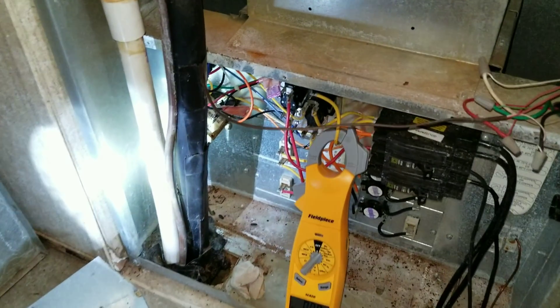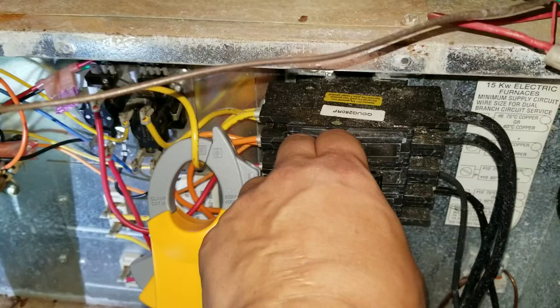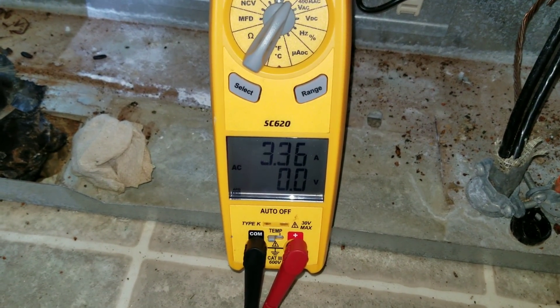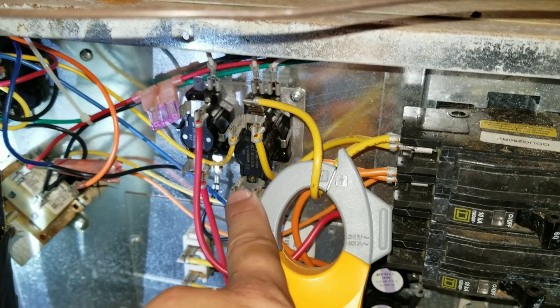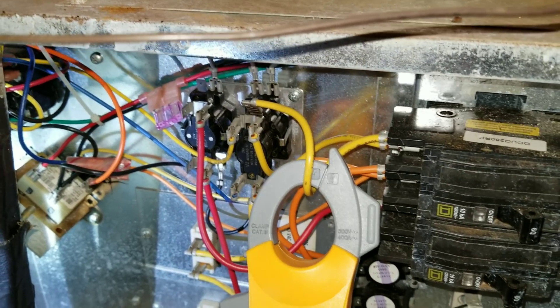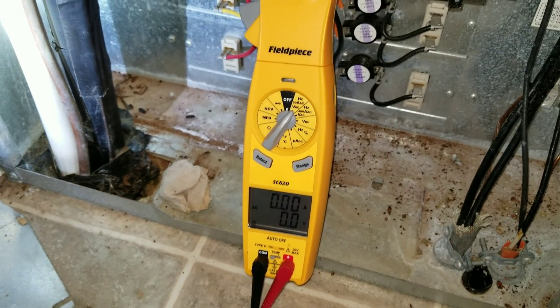But trying to be thorough, I went ahead and started checking the electrical down here. And what I found at first was this breaker was getting hot. The reason why is because one of the heaters keeps coming on and off. You can see the wire that I have clipped — it's not the top sequencer, it's the one directly below it. That sequencer is stuck closed, and this thing has been cycling the heater on and off for a couple months now.